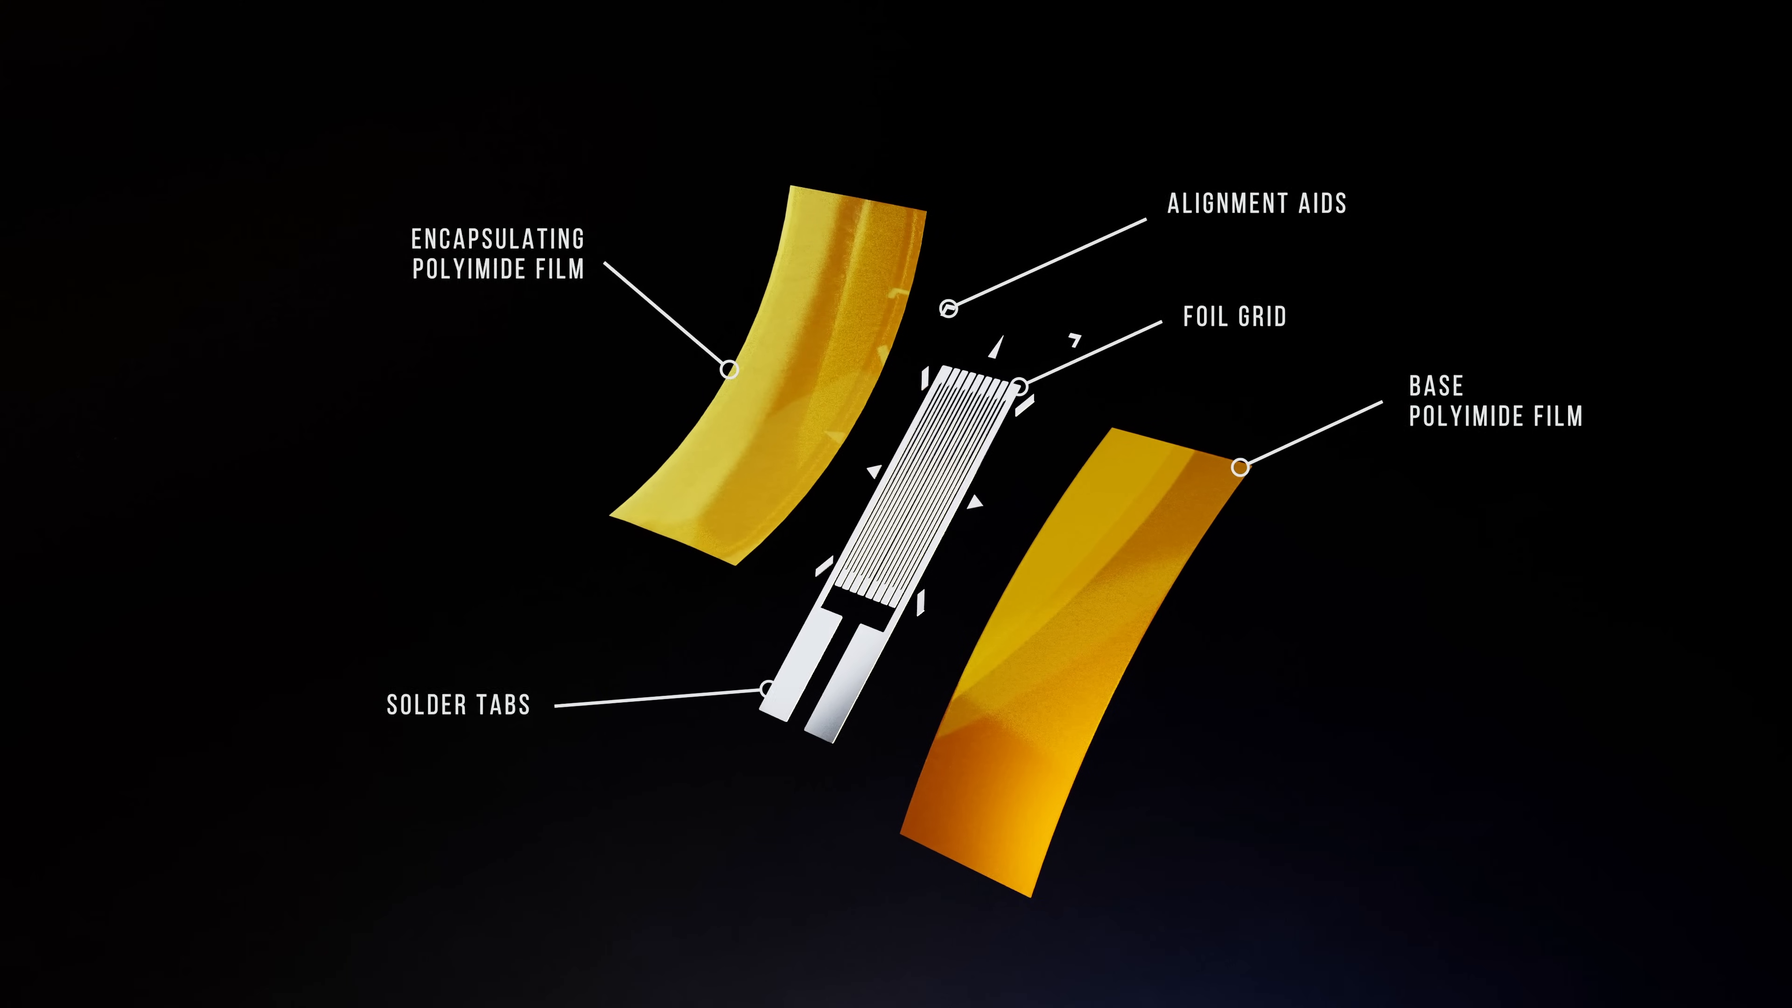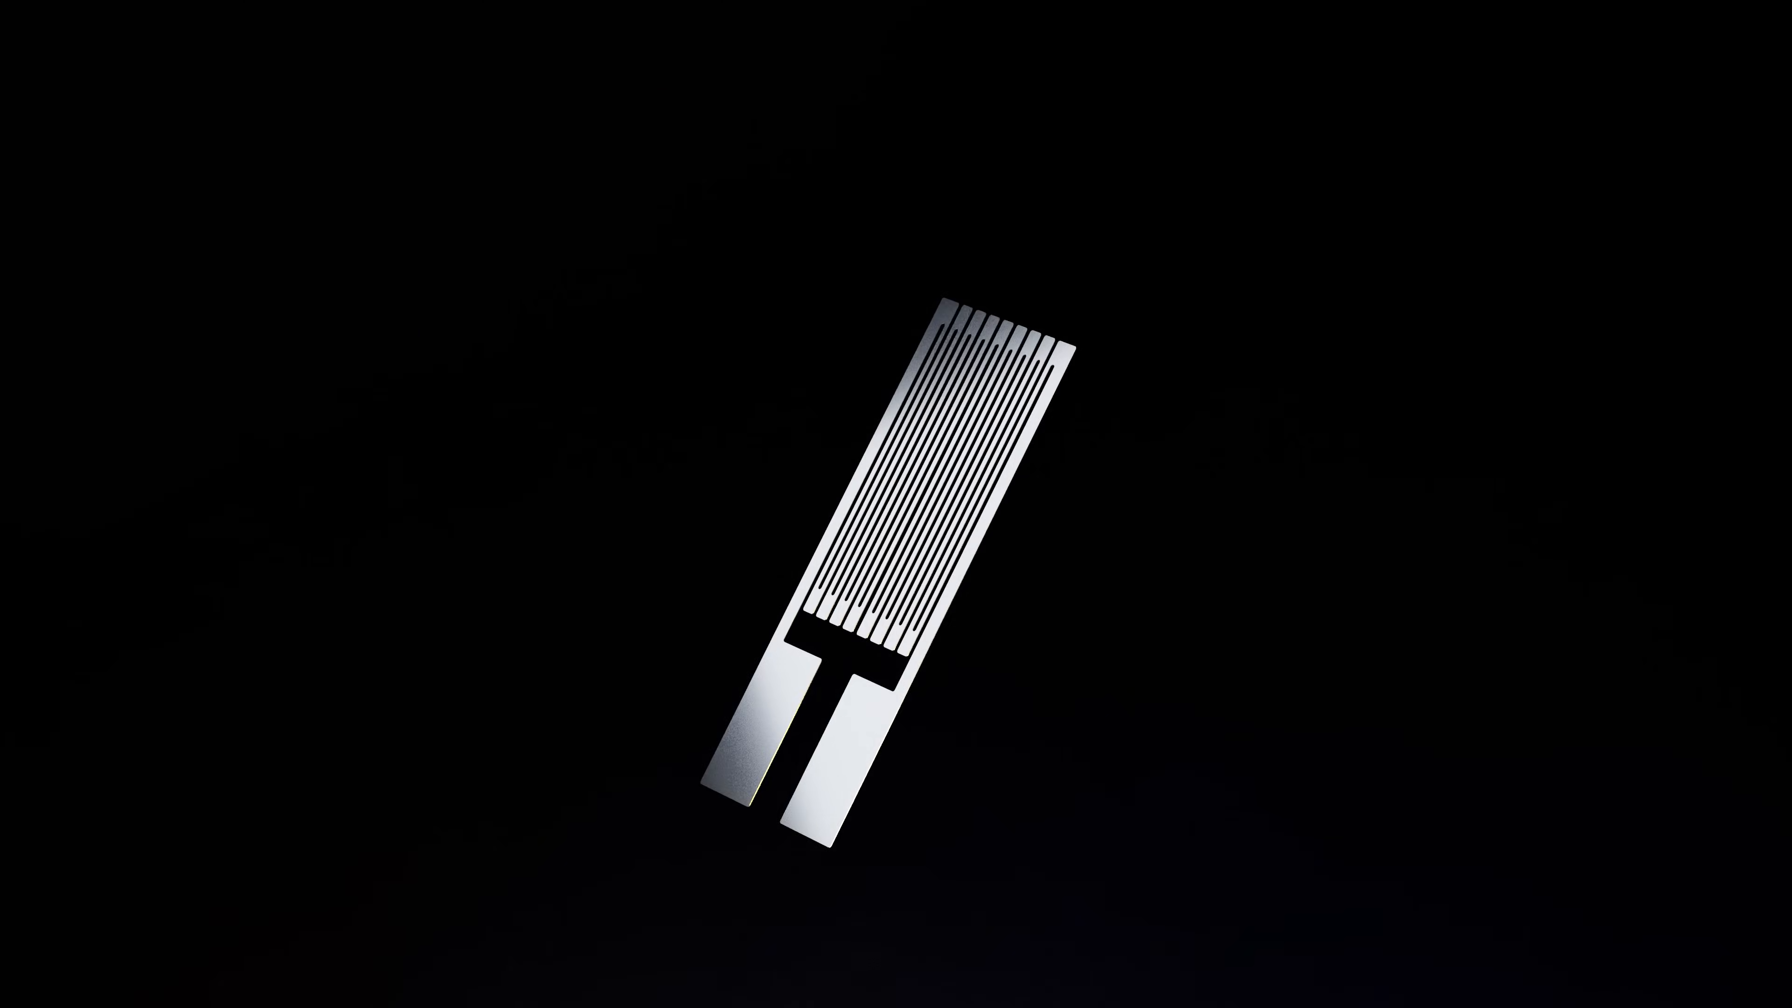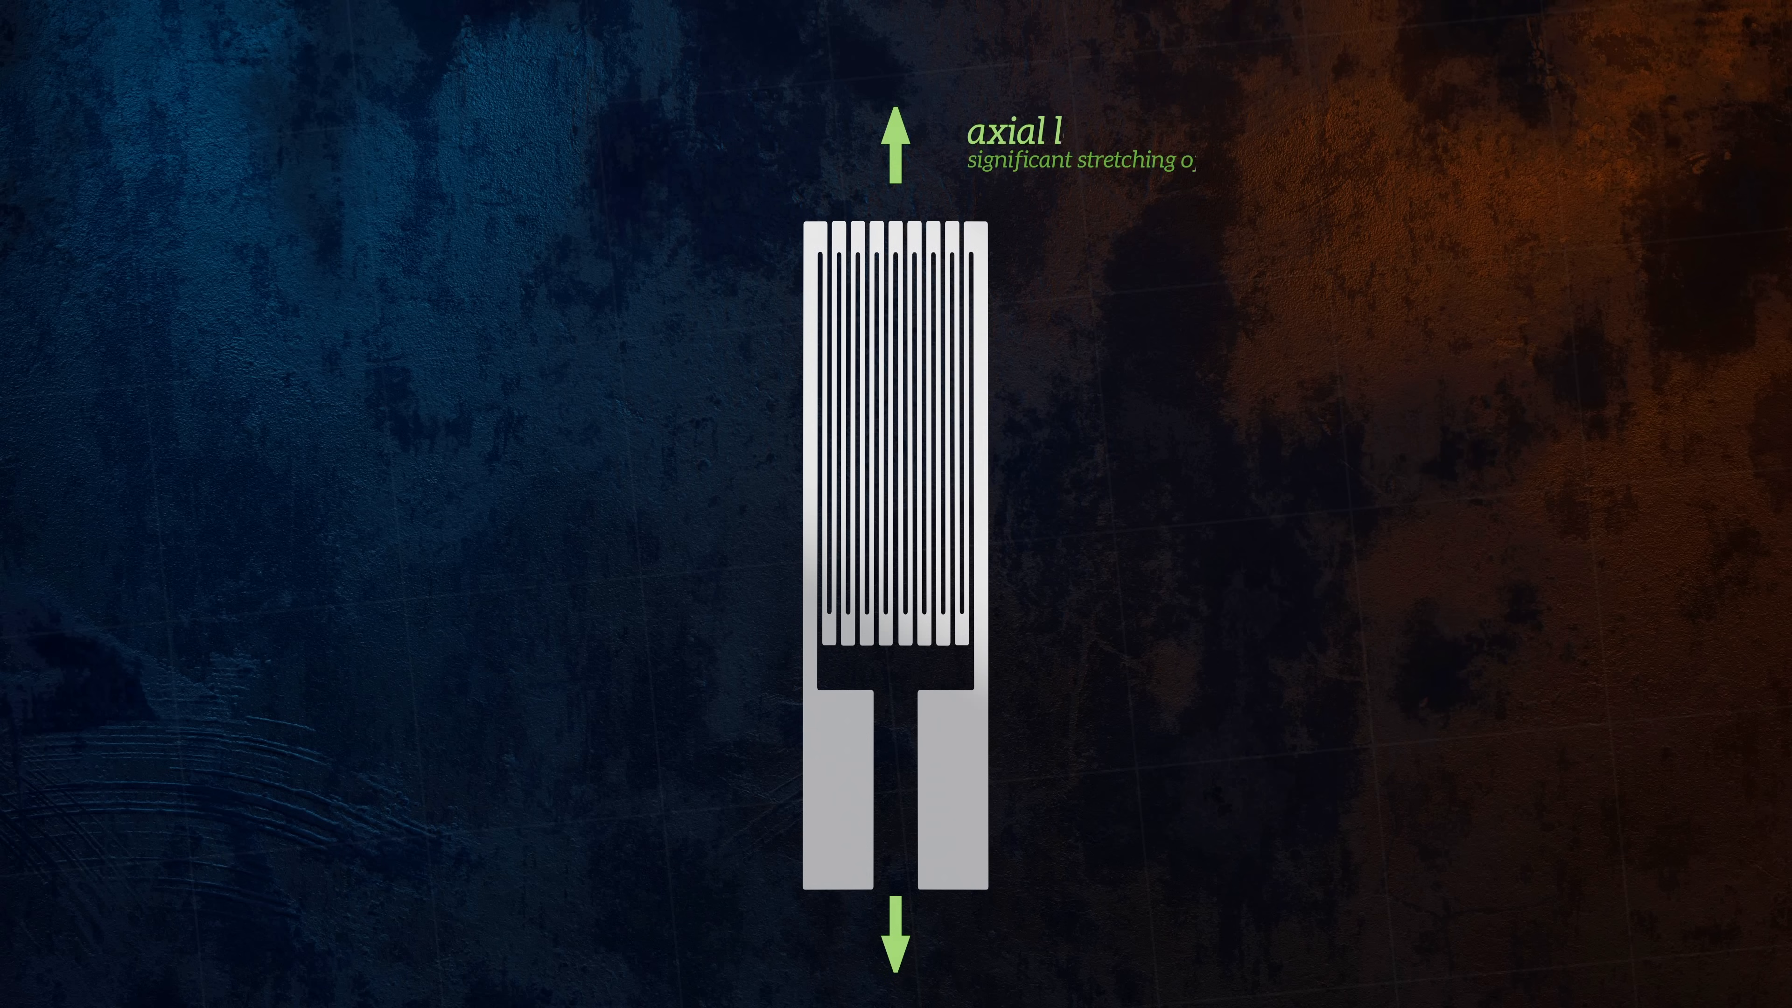The foil grid is where all of the smart stuff happens. It's made from a conductive material that's formed into an intricate pattern using a photo etching process. The pattern is cleverly designed to maximize the amount of material that's stretched or compressed when loads are applied in the axial direction, while at the same time minimizing any stretching or compression of the material when loads are applied in the transverse direction.